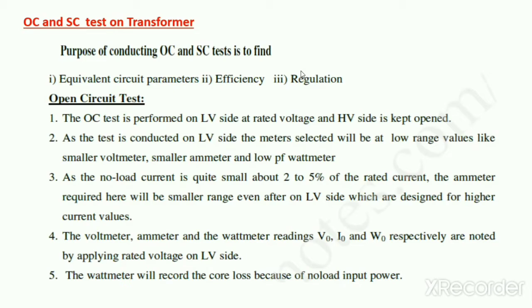Therefore the OC test is conducted on the LV side, and we use low rating meters, that is a small ammeter, small wattmeter, and low power factor wattmeter.